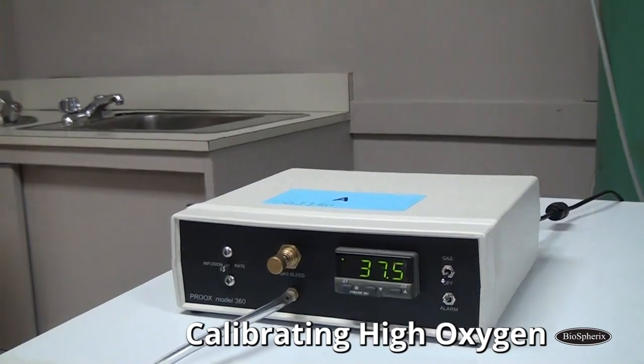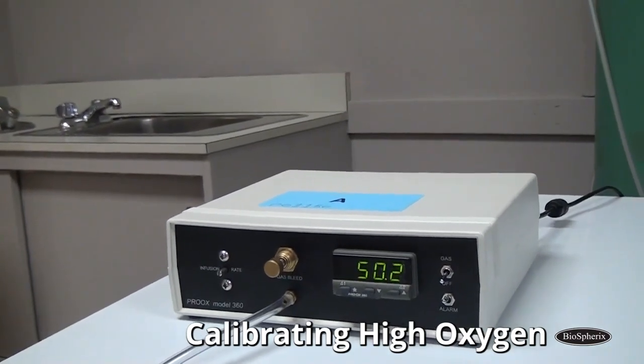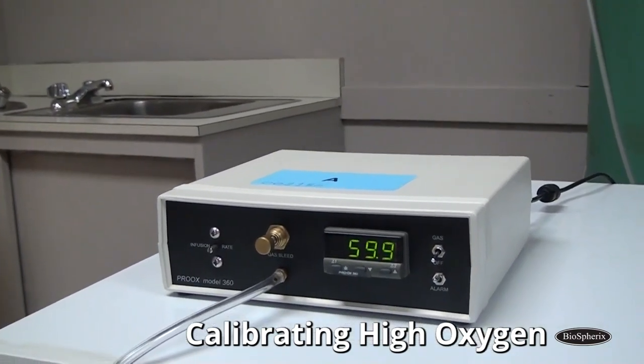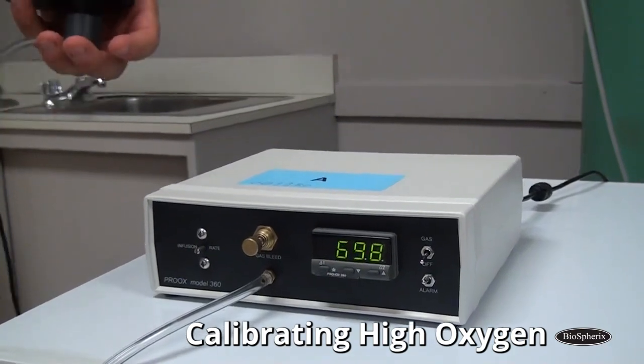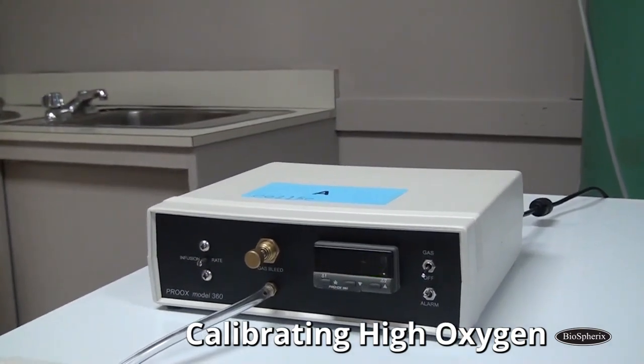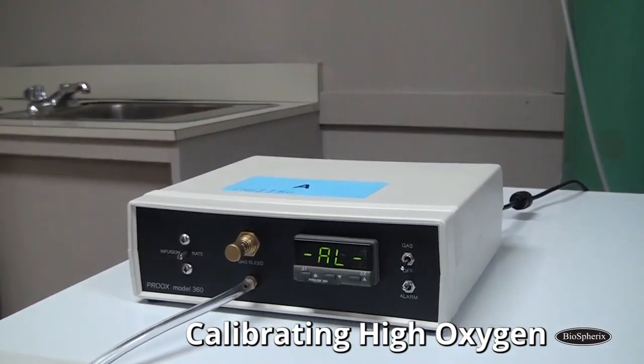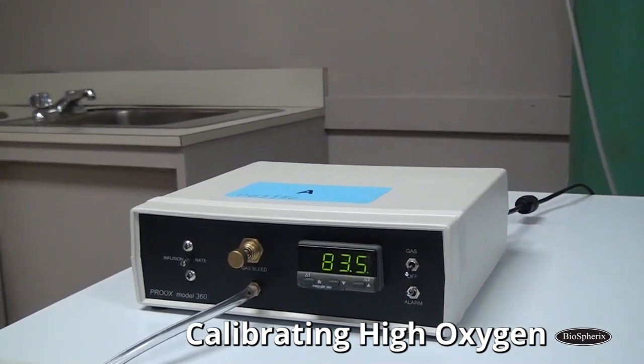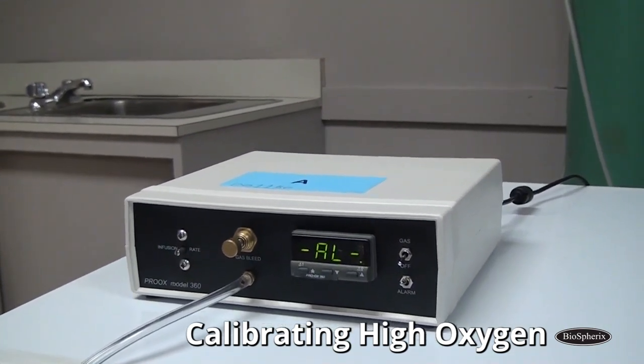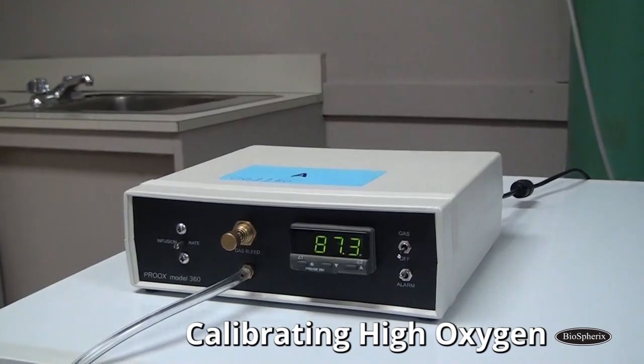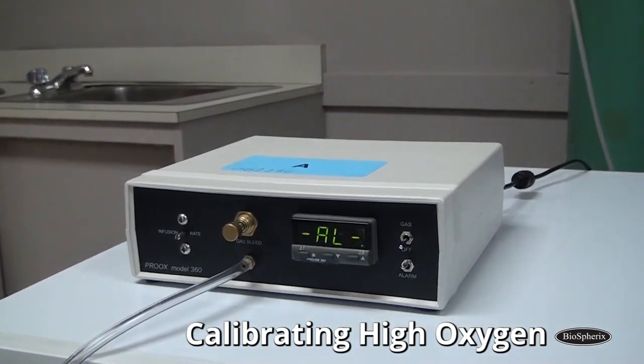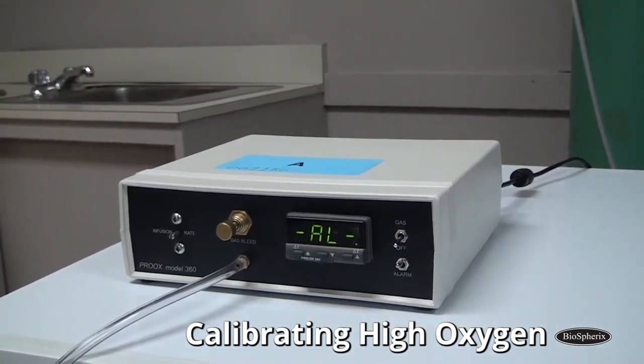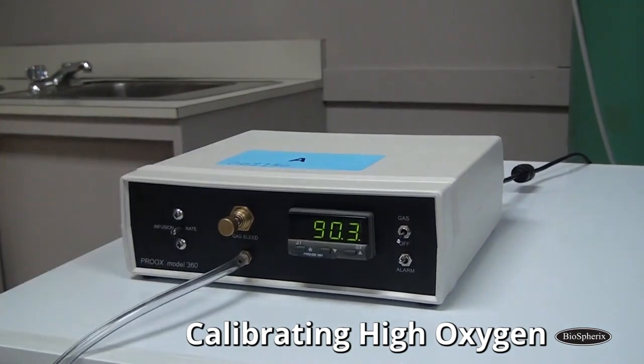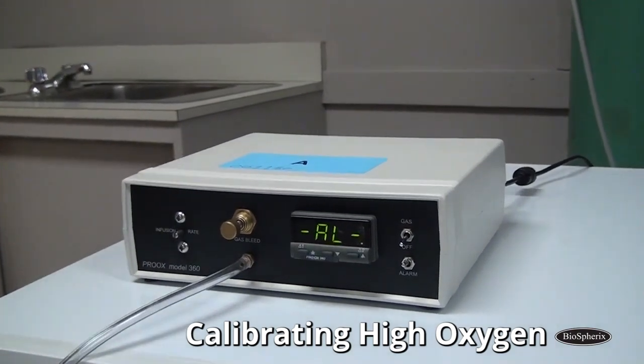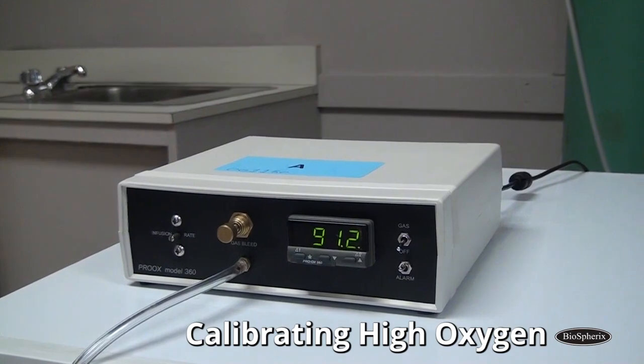So what we're doing now is we're doing our high end, our span calibration, the second part. And we're exposing our sensor to pure oxygen right now, so 100.0. That AL you're seeing is just the alarm setting being turned on there. It just is letting you know that the alarm condition was reached. And again, the span is a coarse adjustment.